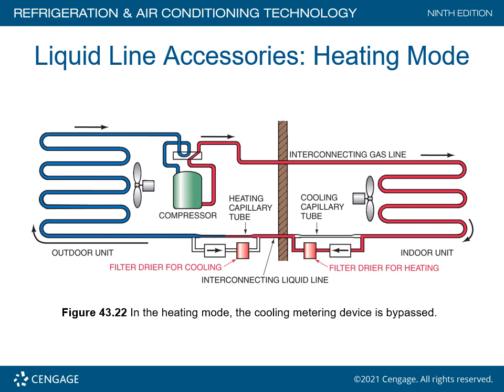So when you're replacing one of these, that connection's easy. Now, could you mess up the connections on the other part? Yeah, you could if you weren't paying attention. That's why it's very critical that you look at how the lines are attached and mark them, just to make sure the replacement valve is put in the correct position. The refrigerant is coming from the outdoor unit in the heating mode. Remember, the outdoor unit, instead of taking heat out of the structure, is actually taking heat from the outside air. And we are going to utilize that heat to heat the house.